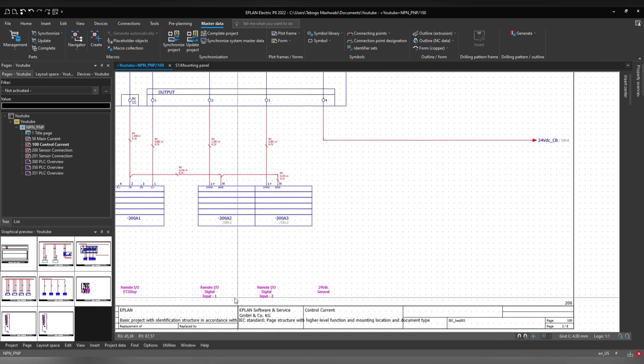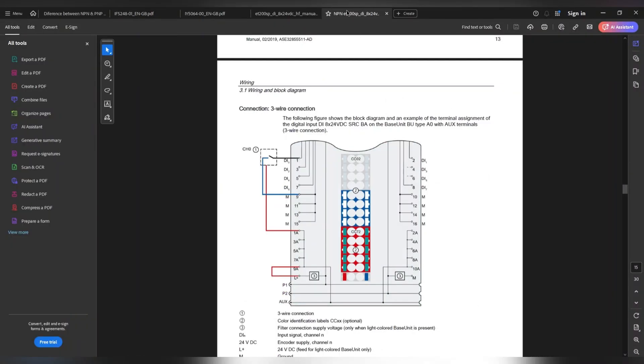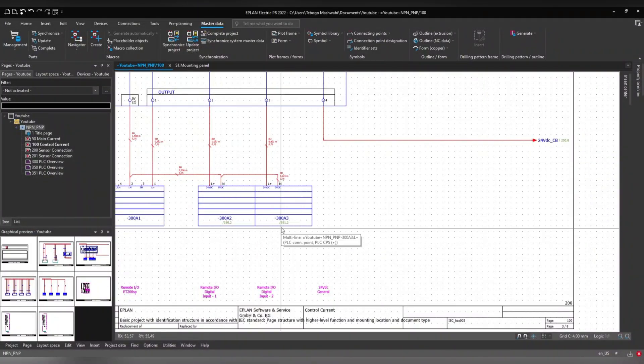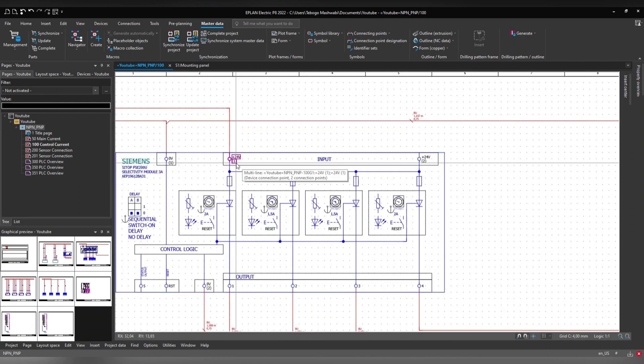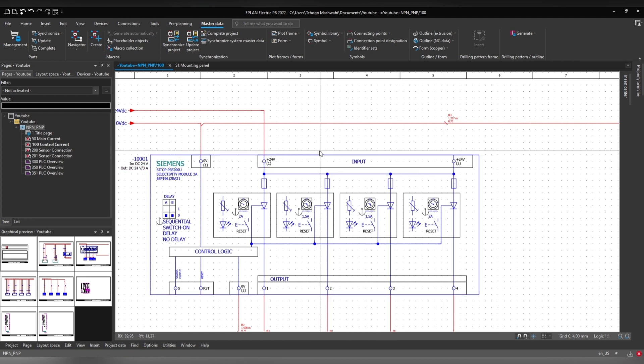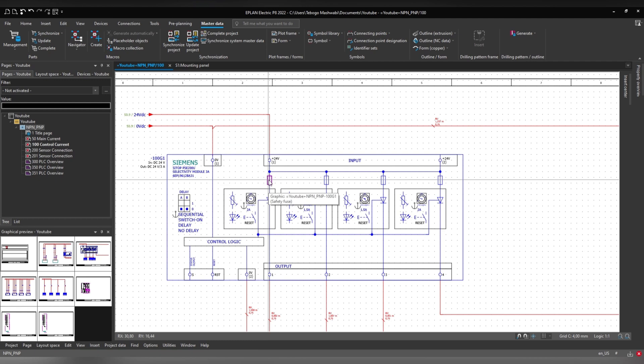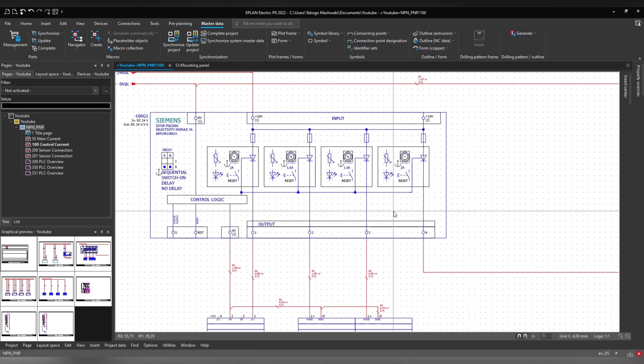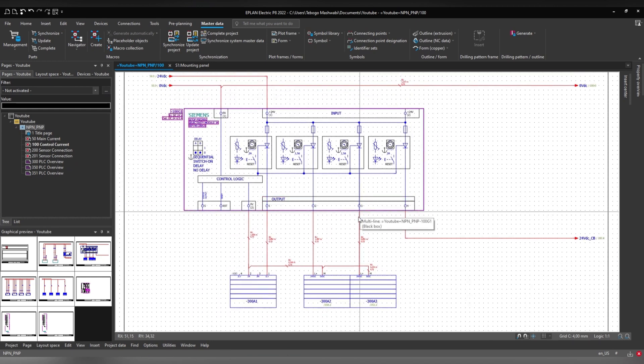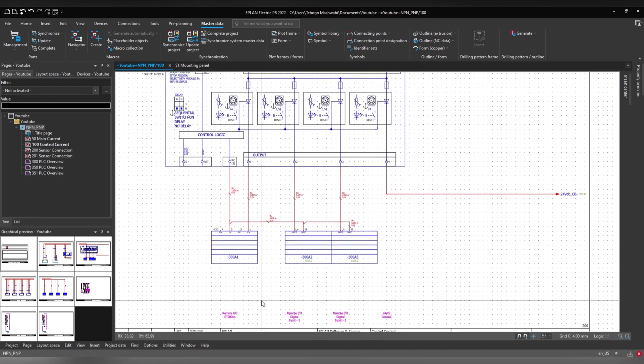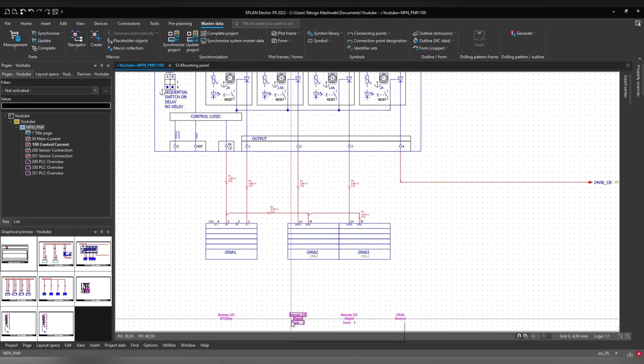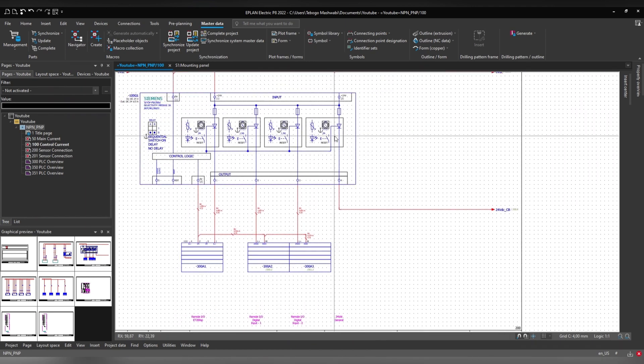These two digital input cards — this is the first one and this is the second one. We give this one 24 volts — this is 24 volts coming from the power supply without monitoring or protection at that stage. Then through this section we give it protection. You can see there are diodes to protect it from reverse polarity or current flowing back into the system, so current only flows toward the remote IO, the first input card, and the second input card.